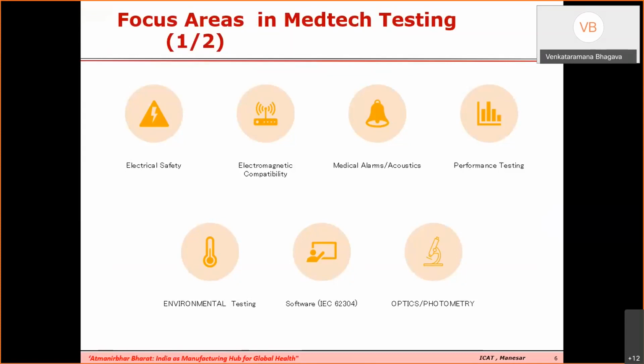And specifically, let us say if a device fails, then it's called a single fault condition. Then what happens is very critical. The second category of tests is the electromagnetic compatibility or EMC testing. This is again very critical in all electromedical devices. So what is EMC? As we know, we live in an electromagnetic environment. Let us say if a patient has a pacemaker and he goes next to a transformer or some sort of a high tension line, it may affect the performance of the device. So this is called electromagnetic compatibility immunity testing.